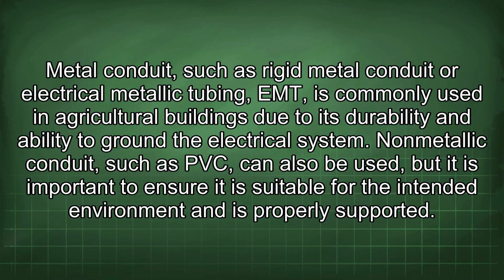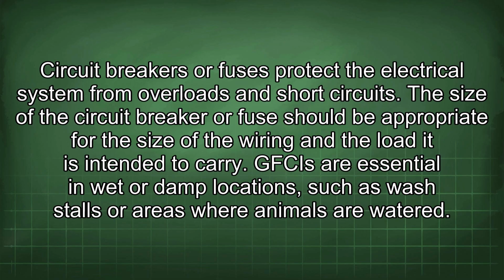Non-metallic conduit, such as PVC, can also be used, but it is important to ensure it is suitable for the intended environment and is properly supported. Circuit breakers or fuses protect the electrical system from overloads and short circuits. The size of the circuit breaker or fuse should be appropriate for the size of the wiring and the load it is intended to carry.